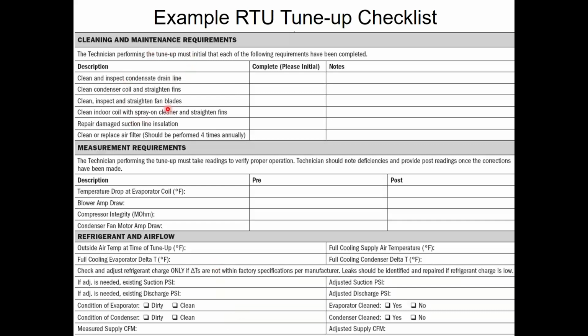So the first section on there is cleaning and maintenance. So cleaning and inspecting. It should really say inspect and clean, right? Because if you inspect it and there's nothing wrong, then there's no reason to clean it, right? But it's just a pet peeve of mine that it's worded that way. So those are the different things you would want to inspect and or clean as part of this maintenance program, and the things you would want to measure before you do that. That's another pet peeve of mine. The pre-measurements should happen before you do the cleaning. You should measure these things, do the cleaning, then measure them again. So it should be listed that way.